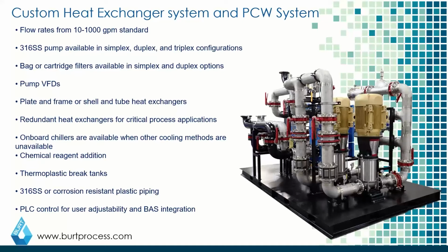Those of you unfamiliar with PCW systems, they're used a lot of times in industry, and specifically semiconductor or medical device manufacturing, where you're trying to do basically a control loop outside of a chiller-based system, where you're basically doing a process chilled water loop. Kind of like the idea of a radiator system, but a little bit different in those cases, where you have a recirculating loop, but you're basically doing temperature control throughout the building.